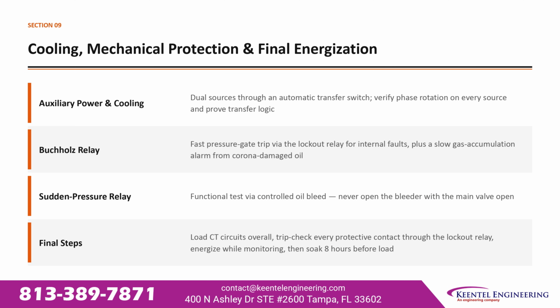Auxiliary power and cooling should run through dual sources with an automatic transfer switch. Verify phase rotation on every source and prove the transfer logic actually works. The Buchholz relay provides 2 layers of protection, a fast pressure gate trip through the lockout relay for internal faults, plus a slow gas accumulation alarm from corona-damaged oil.